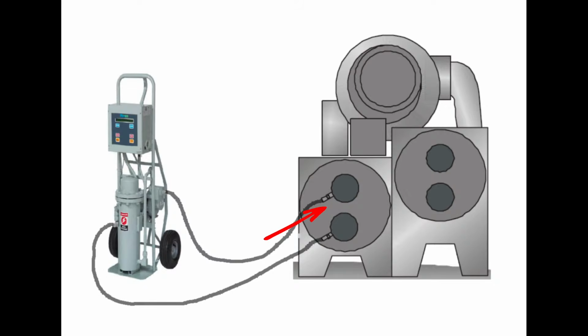Which in absolute, it would be at, say, 12 to 13 psi absolute, not gauge. That means you're sitting below atmospheric and you're in a vacuum, right? And anytime you service this, like change out the purge filters, change your oil filter, do anything of that nature, or if you're trying to take an oil sample from the bottom of the oil sump, all of those things are going to cause you issues and have potential of drawing in atmosphere into the machine.